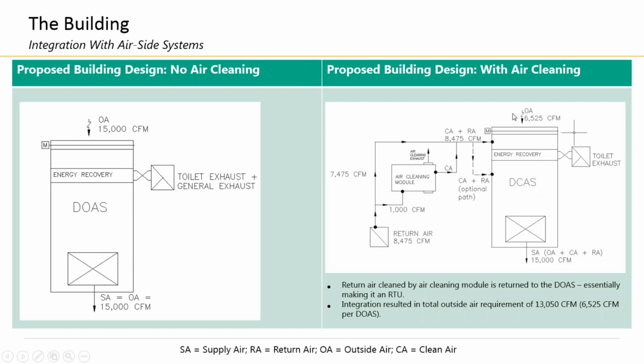By scrubbing this air, you can reduce your outside air requirement from 15,000 down to 6,500 CFM, and your supply air remains constant, so you can continue to take advantage of economizer modes. So your fan sizes will stay the same size, but you can downsize all the rest of your cooling and heating capacity if this was a new design construction. See that happen quite frequently.